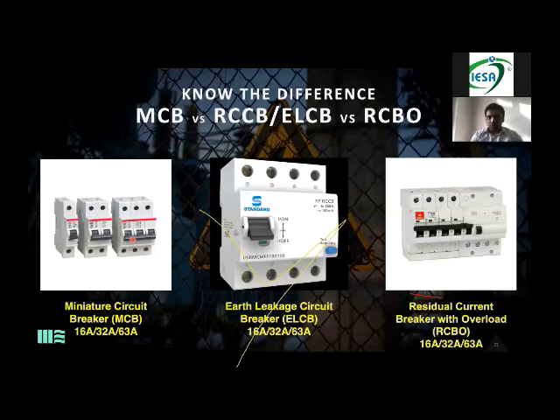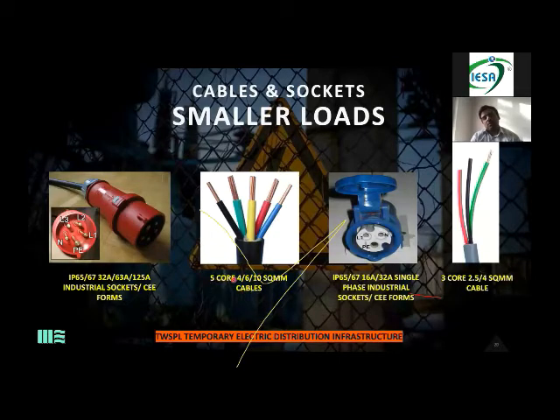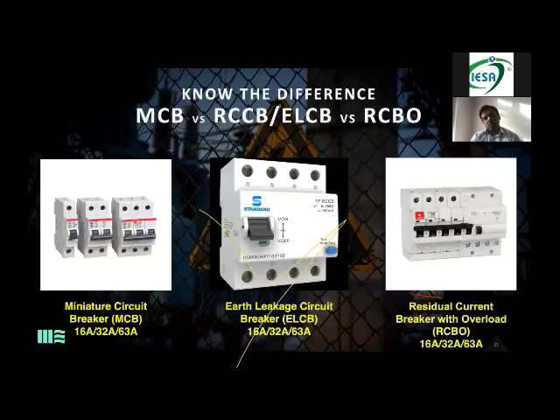Because in an event, you're distributing power to so many people. Maybe there are 600 exhibitors. When we are doing exhibitions, maybe there are 1000 exhibitors participating, and we are giving power to each and every exhibitor according to the load. The load may be shared by the organizer, saying please give them 10 kilowatts. So we know that for 10 kilowatts, we need to use a 4 square mm cable, a 32 amp socket, and at the end point I need to give them an MCB or an ELCB or an RCBO. We'll go into the difference. So it saves me from 2 major things, short circuit and overload.